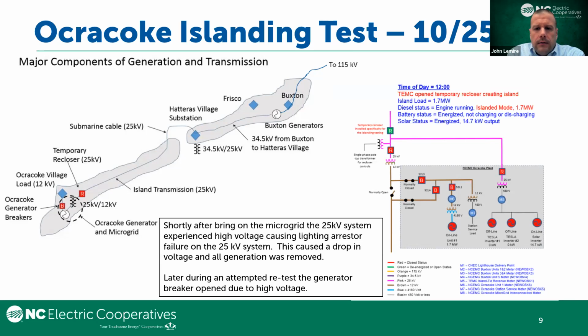So, post-event analysis and looking at the event, at first we weren't really sure what happened. Further analysis showed that when we were running the batteries on the 25 kV system, due to our transformer configuration, we did not have an effective ground reference for the battery system to reference and to regulate the voltage. And so the good thing is that was limited to the 25 kV system. For the technical people, it was a delta to Y transformer, and that delta high side didn't provide us the effective ground.